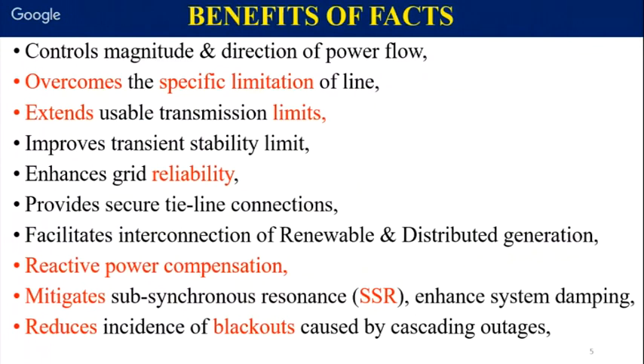As you know, FACTS have immense benefits. They control the magnitude and direction of the power flow. They overcome specific limitations of a line. Suppose we want to maintain the voltage profile or control the power transmitted, FACTS can be the best option. They improve the transient stability limit. During dynamic response, you will get a good dynamic response with FACTS. They enhance grid stability and provide secure line connections. Also, they facilitate interconnection of renewable and distributed generation. Reactive power compensation is most effective with FACTS. They also mitigate subsynchronous resonance, enhance system damping, and reduce instances of blackout or cascading outage.